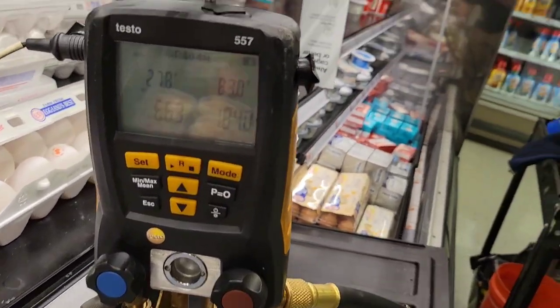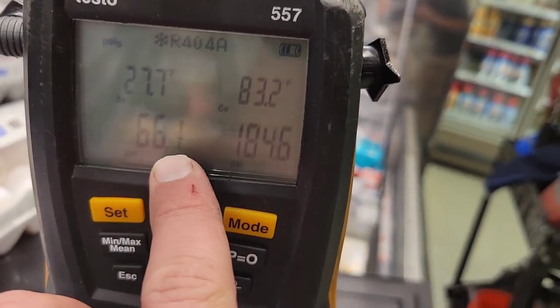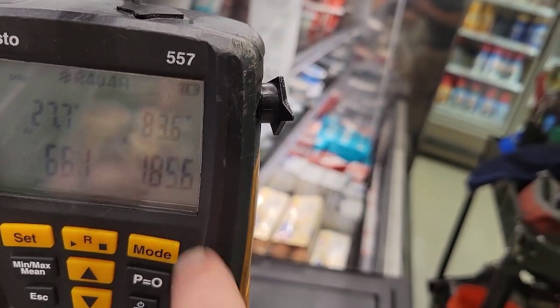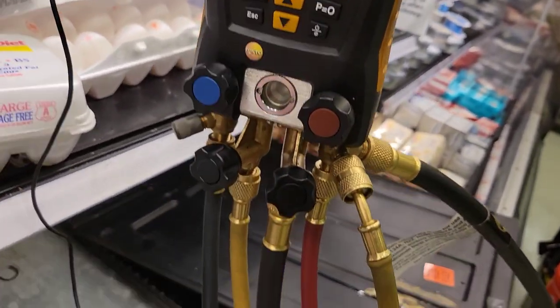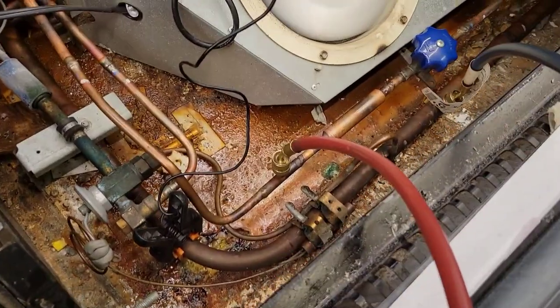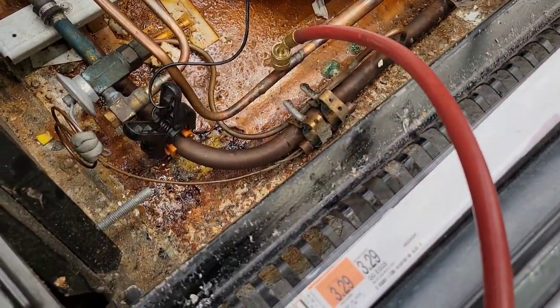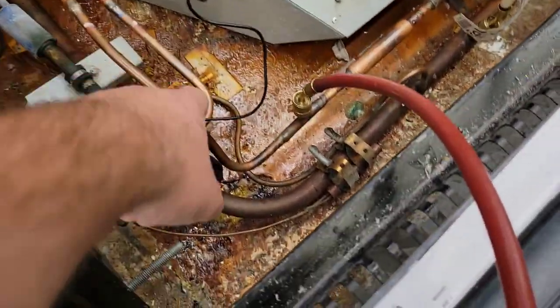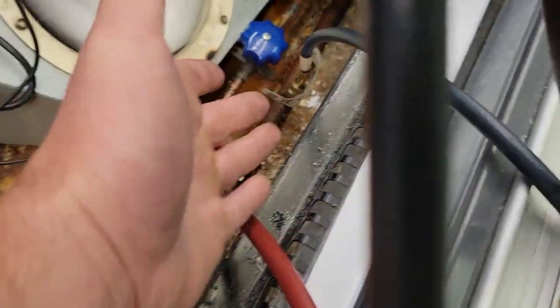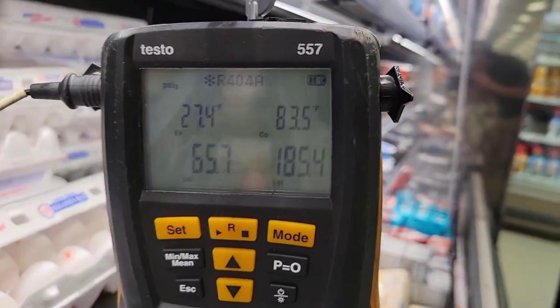So you can see right now I have pressures hooked up: 66 degrees, which is a 27 evap, which is okay, and 182 liquid pressure, which is okay. Anyway, I hooked up my temperature probe at the end of the coil right before the TXV valve. You can hook it up after if you want. And we're gonna take superheat.